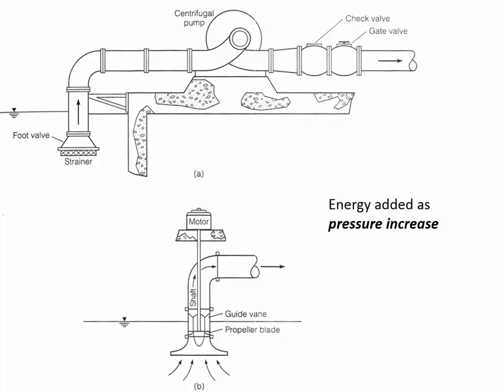In the case of this axial flow pump, you'll notice that the advantage here is that the impellers you can make below the water line, and so priming this pump isn't going to be an issue because the water is already in contact with the vanes. And so as soon as you turn it on, that water is going to start flowing through the pipe. It doesn't need to create a suction to begin with.